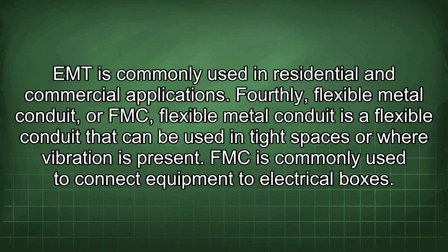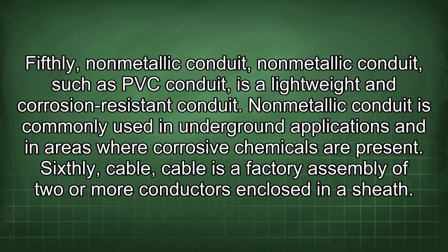Fourthly, flexible metal conduit, or FMC. Flexible metal conduit is a flexible conduit that can be used in tight spaces or where vibration is present. FMC is commonly used to connect equipment to electrical boxes. Fifthly, non-metallic conduit. Non-metallic conduit, such as PVC conduit, is a lightweight and corrosion-resistant conduit. Non-metallic conduit is commonly used in underground applications and in areas where corrosive chemicals are present.